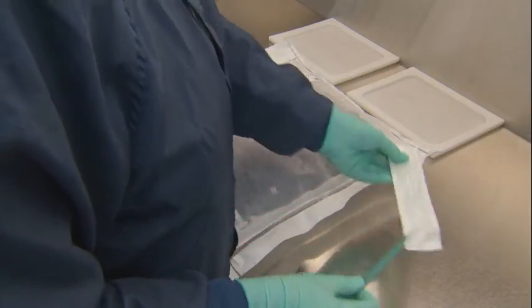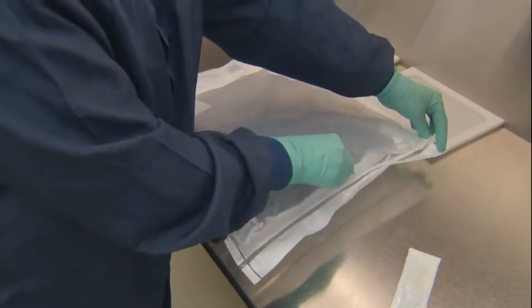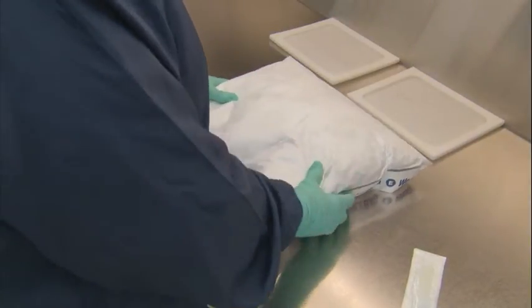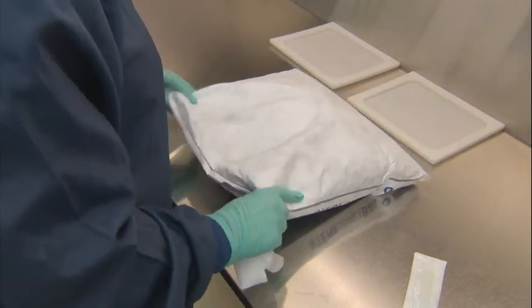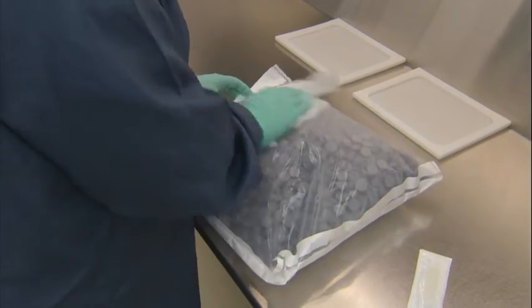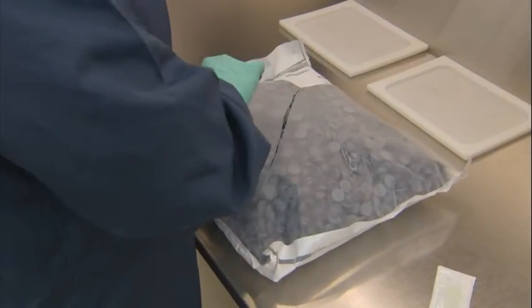Place the bag flat with the Tyvek side down and cut the bag with a scalpel. Lift out the primary bag containing the product and place it in the inspection area. Again, wipe the outer surface in the same direction with overlapping strokes using lint-free alcohol wipes. Cut the HDPE side of the sterilizable bag in an H or X shape with a scalpel.